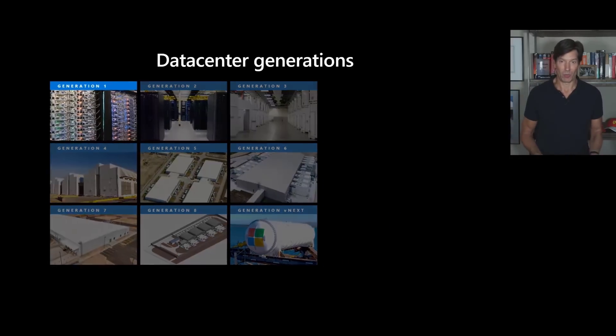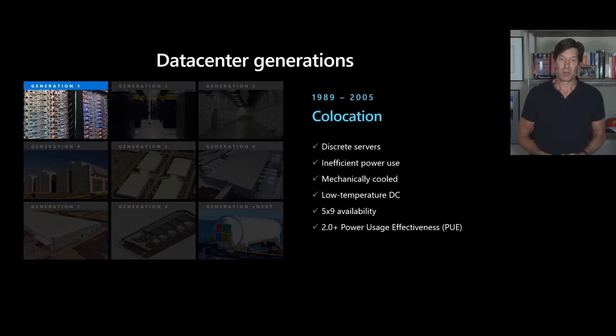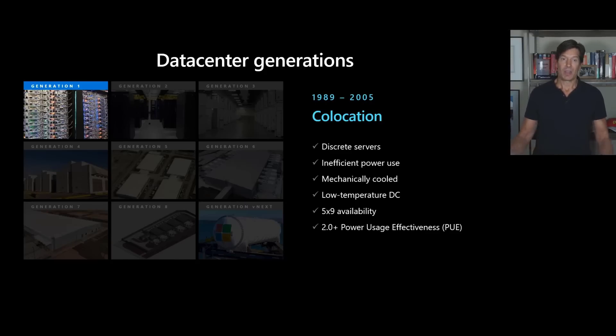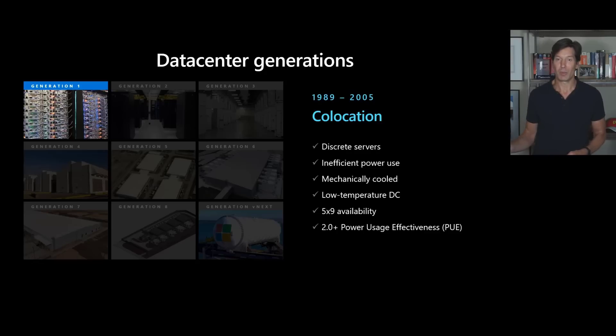Starting back in generation one — the colo era for Microsoft — we were deploying discrete servers of all different types into colo facilities that were mechanically cooled, operated at low temperature, and delivered five-nines availability with redundant power to every server. With this colo approach and no focus on efficiency, our PUE was 2.0 or higher. This isn't far off what most enterprises are experiencing today, because most enterprises still operate in this colo manner.